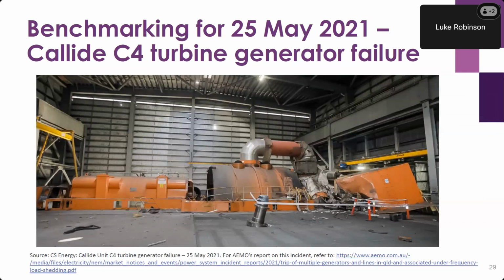That was a bit of background to the methodology, but another part of the risk review process is that we do benchmarking of our modelling approach against real power system incidents. One of these incidents was the Callide C4 turbine generator failure on the 25th of May 2021, as shown in the picture, where an initial issue at Callide resulted in cascading failure, the trip of multiple generators and lines in central Queensland, and the operation of more than 2 gigawatts of associated under frequency load shedding.